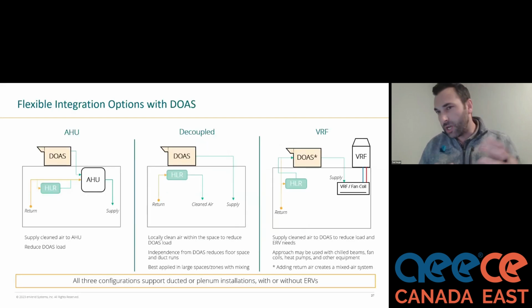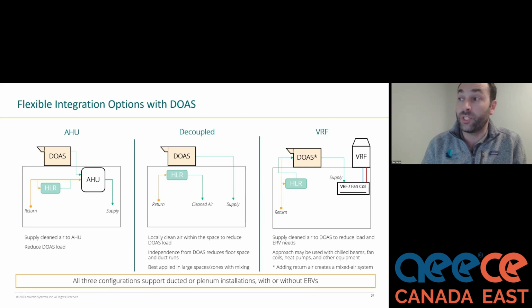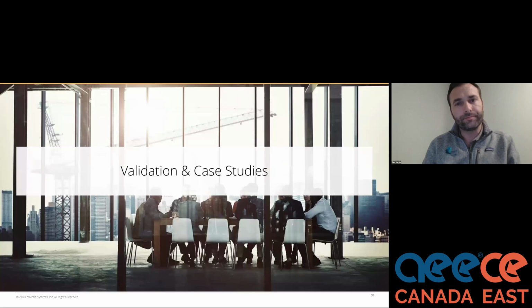We get asked a lot, because we talk a little bit about return air, can this be integrated with DOAS applications? Absolutely. The IAQp can be designed with pretty much any system type. So you can apply it in a decoupled manner, serving large volumes of air, like, for example, a large auditorium, a church, a hotel conference center. You can also place this into mechanical rooms and help shrink the size of those DOASs up on the roof, because you now only need to bring in enough outside air essentially for building pressurization. We are also well paired with VRF applications.